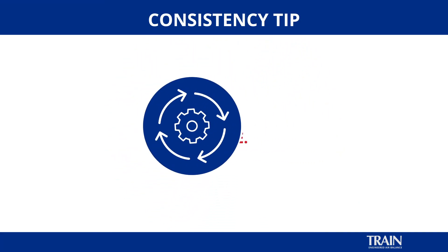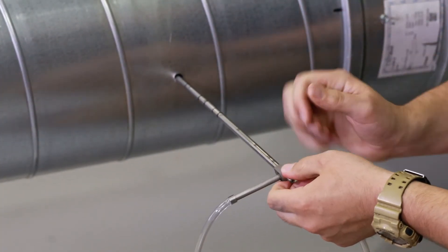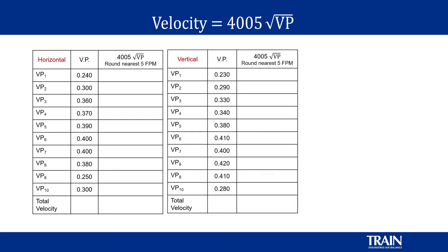We take a static pressure at our traverse location. We will remove the hose on the total pressure port of the pitot tube and record our reading. Now that we have finished our pitot tube traverse, we need to ensure that every single velocity pressure is converted into a velocity. That calculation is the square root of the velocity pressure times 4005. This velocity is then calculated for each individual velocity point that was measured in the duct.